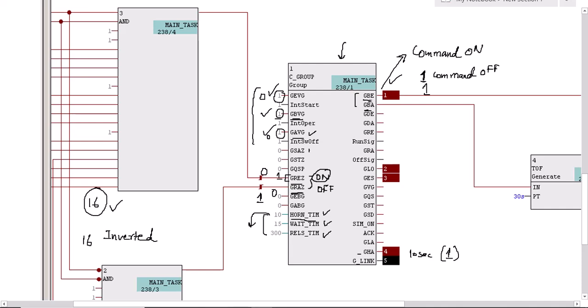A pulse at command on (GBE) is linked with the C Drive block's command on input interface. Whenever a pulse is generated it goes directly to the C Drive block's command on input, and the drive will start operating. Similarly, a pulse at the command off output interface (GBA) is linked with the command off input interface of the C Drive block, and that respective drive will stop operating.